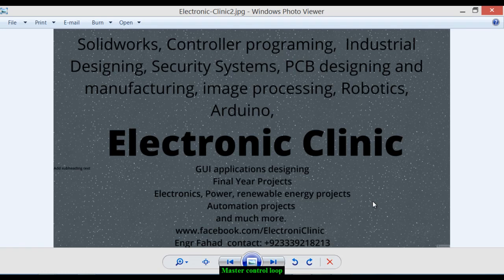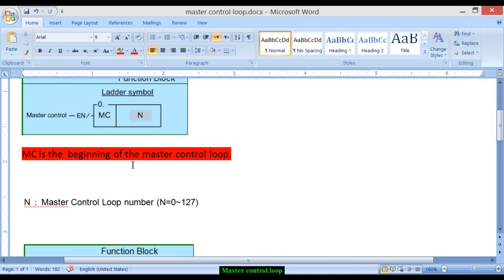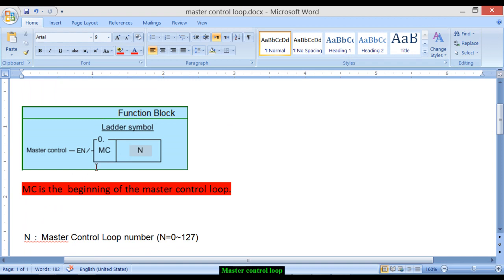Welcome to another Electronic Clinic video tutorial. Today's topic is the Master Control Loop. Let's start with its function block and ladder symbol MC. MC is the beginning of the master control loop. Every master control loop starts with the MC instruction and a number. We have a total of 128 master control loops, numbered 0 to 127.